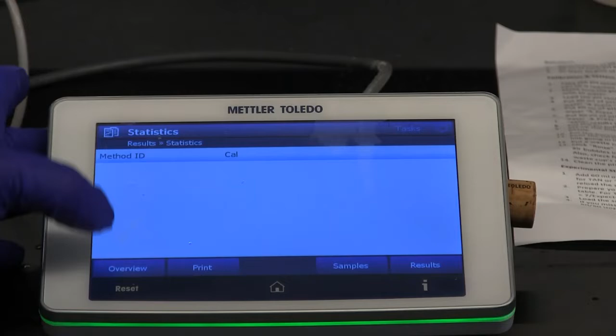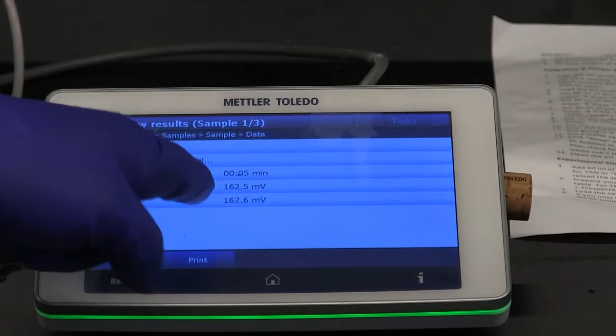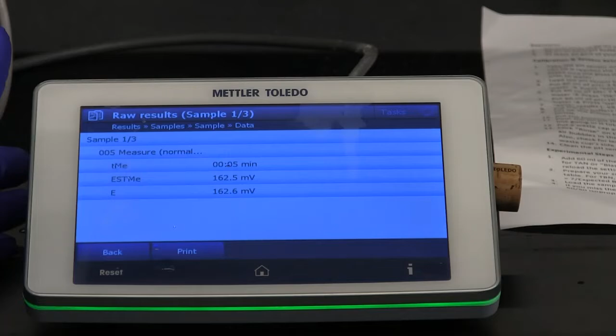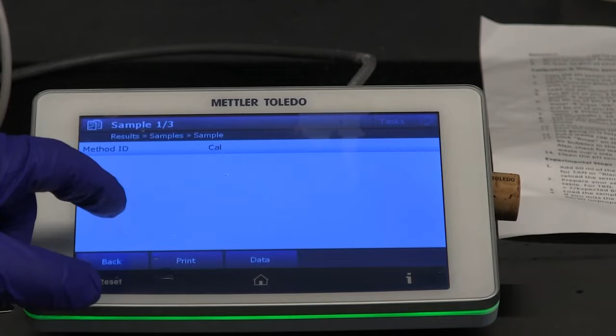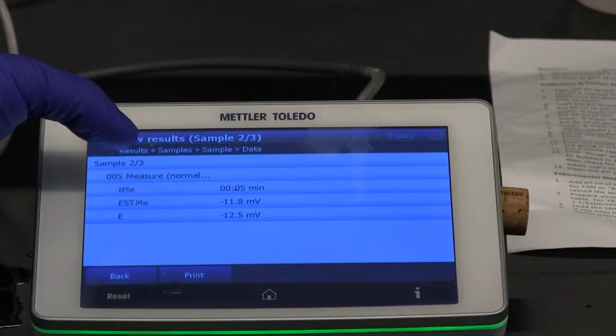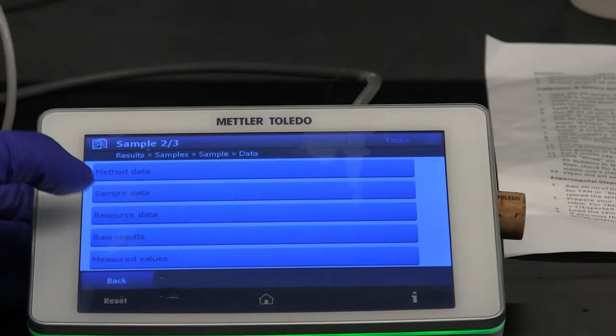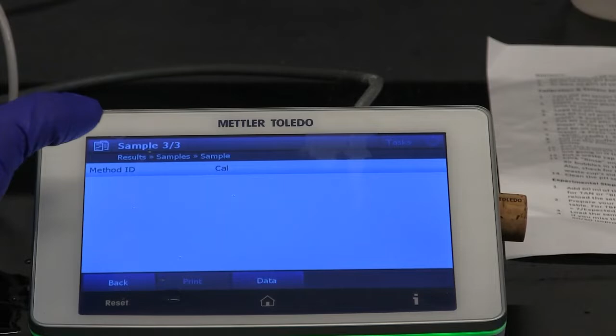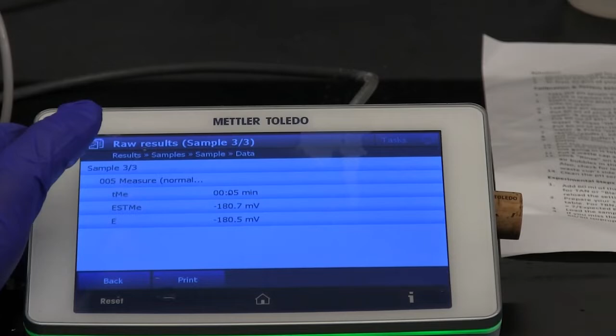From here, results, and then results, samples, click on one, data, raw results, and you have this time 162.5, which is fairly close to 177. If it goes below 160, then it's a problem. And then we go back to the second one, and now it's like minus 11.8, which is close to 0, so it should be fine as well. And the last one is minus 180, which is close to minus 177, so also it should be fine.